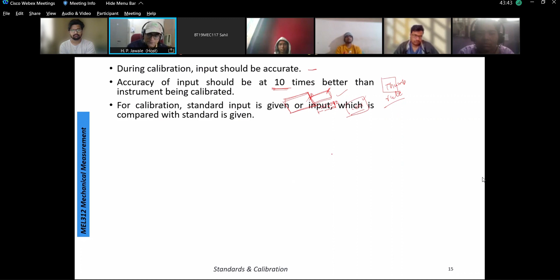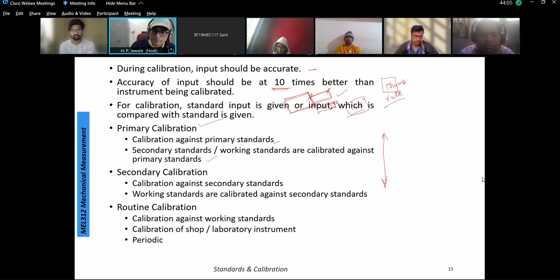It's very obvious now. So for calibration, a standard input is given, or an input which is compared with the standard is given. In primary calibration, the calibration against the primary standard is done, whereas for the secondary standard, working standards are calibrated against the primary standard. This is what we were discussing in the earlier slide. So secondary calibration is calibration against the secondary standard. I think this is some routine method of comparison. Calibration against a working standard is for routine calibration. Say for example, the steel rule that I am going to use in the fitting shop, in our workshop, will be calibrated with the working standard that is kept somewhere in the workshop itself, at some condition, in a preserved way.